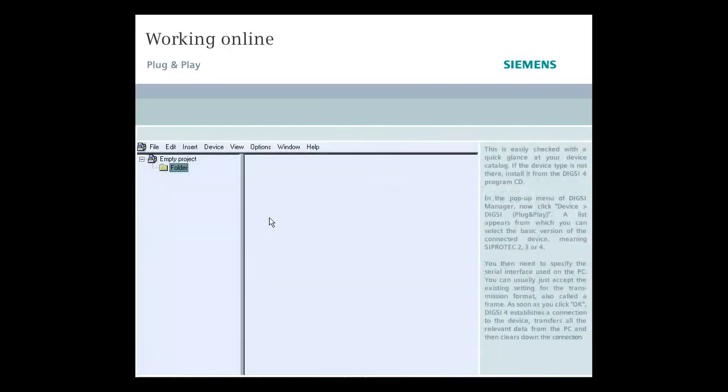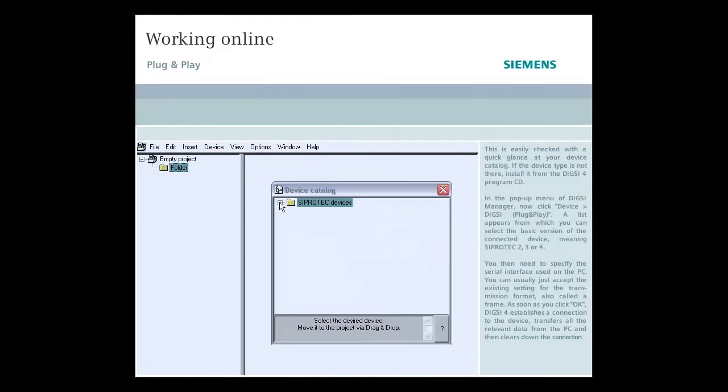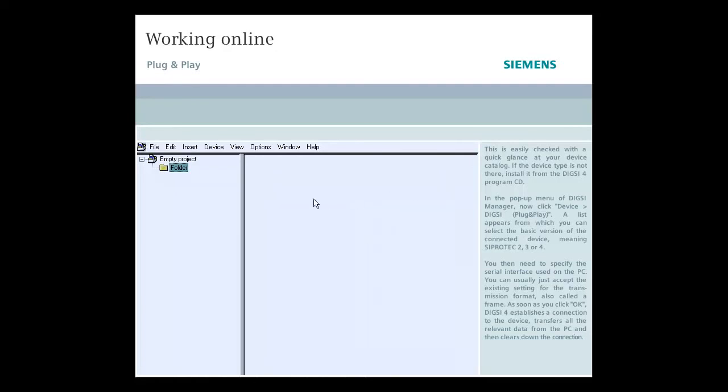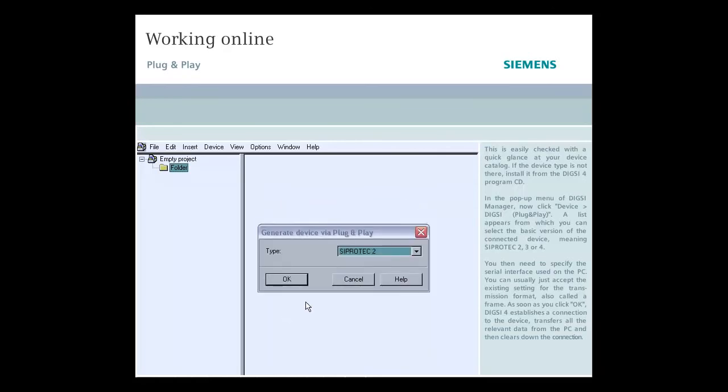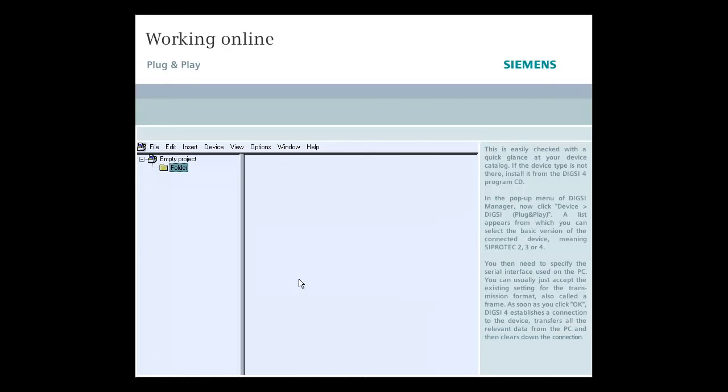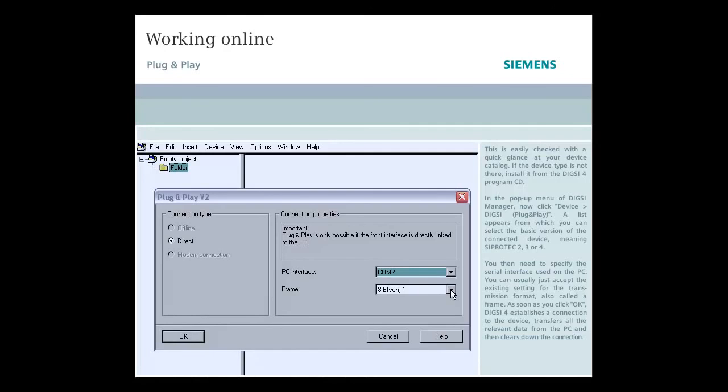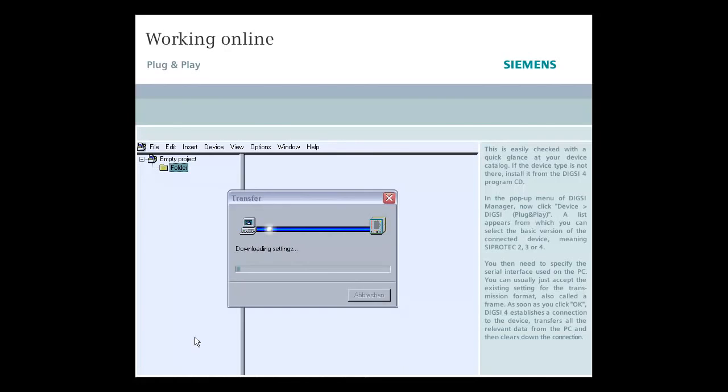The only condition is that the default parameter record of the destination device type is installed on your computer. This is easily checked with a quick glance at your device catalog. If the device type is not there, install it from the DIGSI 4 program CD. In the pop-up menu of DIGSI Manager, now click Device DIGSI Plug and Play. A list appears from which you can select the basic version of the connected device, meaning SIPROTEC 2, 3, or 4. You then need to specify the serial interface used on the PC. You can usually just accept the existing setting for the transmission format, also called a frame. As soon as you click OK, DIGSI 4 establishes a connection to the device, transfers all the relevant data from the PC, and then clears down the connection.